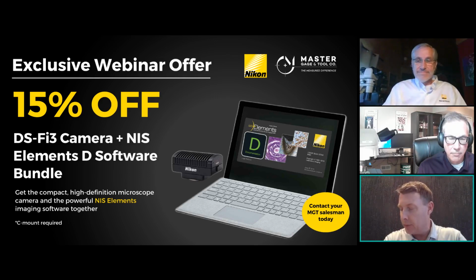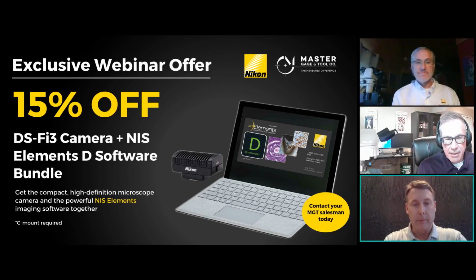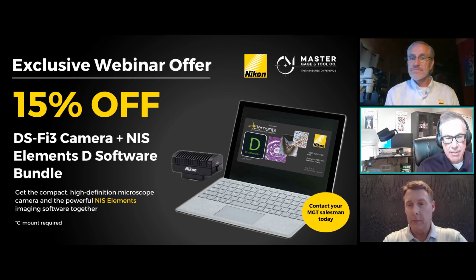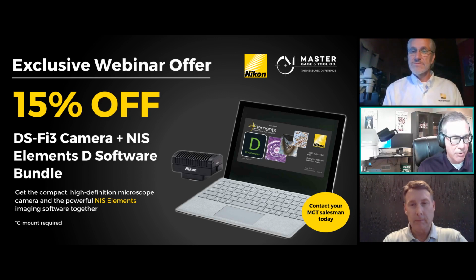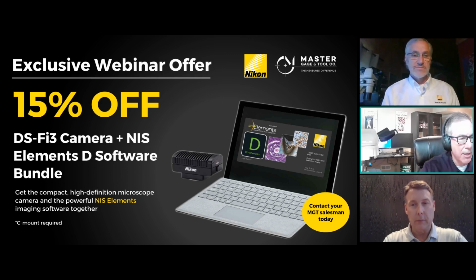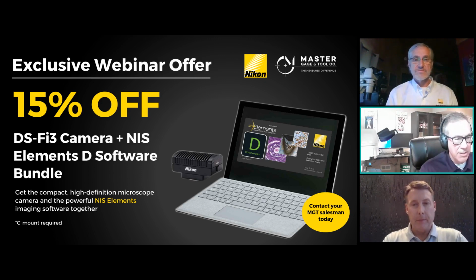Rob, how accurate are the measurement tools in Elements? Well, accuracy is really going to depend on the magnification that you're using, but you saw earlier the calibration values. Each magnification had a value. For instance, on the 50x objective that I was using, 1 pixel was 0.17 microns. So 0.17 microns is the size of 1 pixel making up that image. Of course, you couldn't measure something based on 1 pixel. I give a rough estimate of 8 to 10 pixels to measure something. So if I multiply the 0.17 times 10, that's roughly what the accuracy or precision of the measurement would be at that magnification with that camera and microscope.